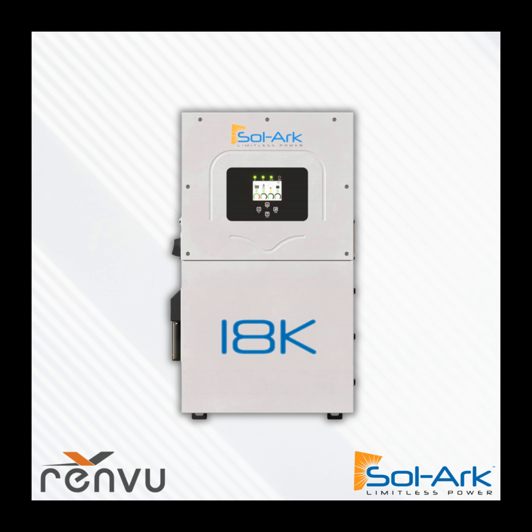Now, all of our inverters, our specialty is in all-in-one hybrid inverters. And what that means is we don't combine the battery and the inverter together. We keep them separated, but we try to package, what in other products would be balance of system equipment, into our inverter -- what you need for grid interconnection for whole home backup. That means the inverter becomes a hub. You can connect solar to it. You can connect batteries to it. You can connect the grid straight to it. It has a port for the load. So whatever power the inverter can't provide, it'll pass through grid power to fully power a 200 amp service.